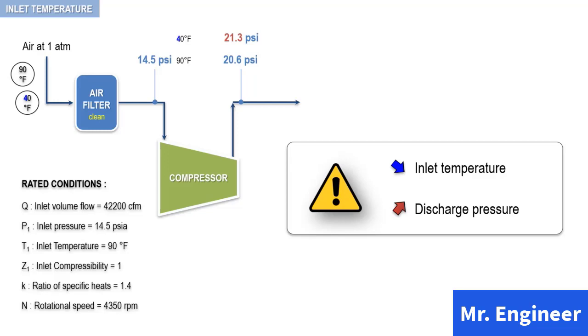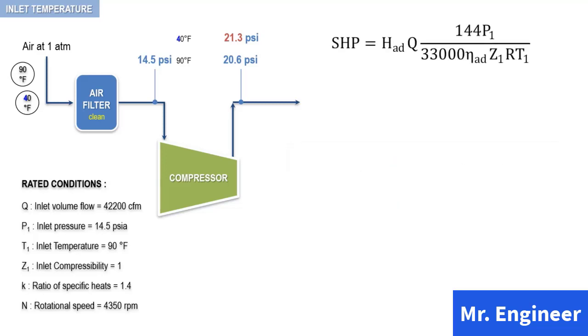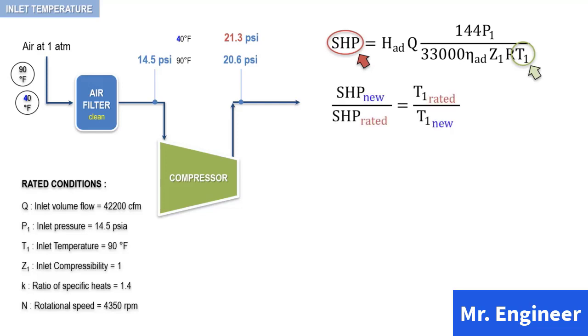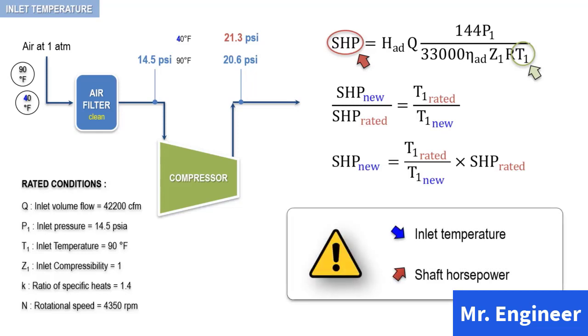As you can see, reducing the inlet temperature will increase the discharge pressure. Let's now examine the effect of the reduction in inlet temperature on shaft horsepower. Referring back to the shaft horsepower equation, without taking into account the mechanical losses, we find that shaft horsepower is inversely proportional to inlet temperature. So we can derive the following useful relationship: a decrease in the inlet temperature will result in an increase in the shaft horsepower.